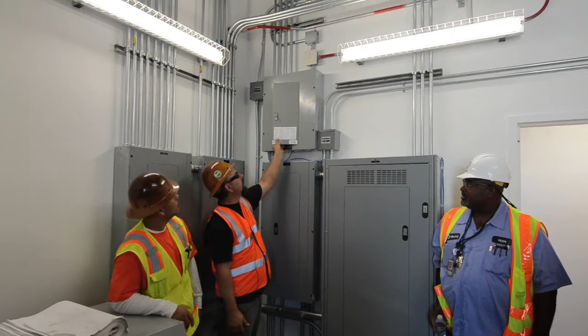You've got hand-off-auto. Right now we're in auto. The relays that are lit now are the loads that are supposed to be on now. The ones that are off now are all controlled by photocell, as I show here on the control type columns. And again, it's not like there's a photocell for this panel and a photocell for that panel. That photocell I showed you on the light pole, it does them all. And that interior photocell down below that I showed you, right now it's hooked up, but it's not programmed to do anything, because I told you I didn't want to turn those lights off downstairs.